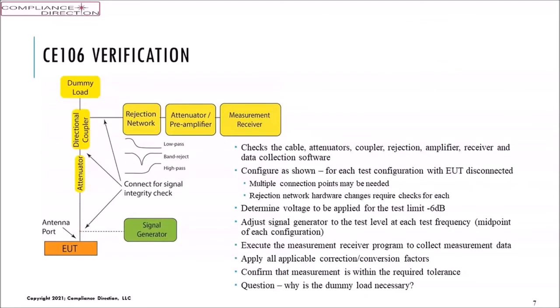Most laboratories use spectrum analyzers as an alternative to the receiver. The receiver provides us a little bit better sensitivity and more ranges. It also allows us, especially in the current receivers that have a lot of bandwidth, to do the fast Fourier transform, etc. Those are allowed to be used. So it's a little bit more common today to see the use of a measurement receiver. However, spectrum analyzers have been used for quite a bit. Now, the difference being their sensitivity, dynamic range, etc. However, also some spectrum analyzers do not have what's called an EMI measurement mode.